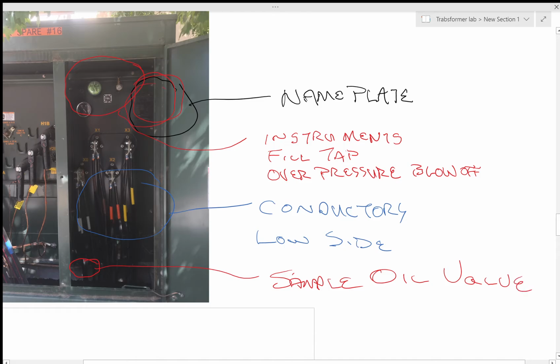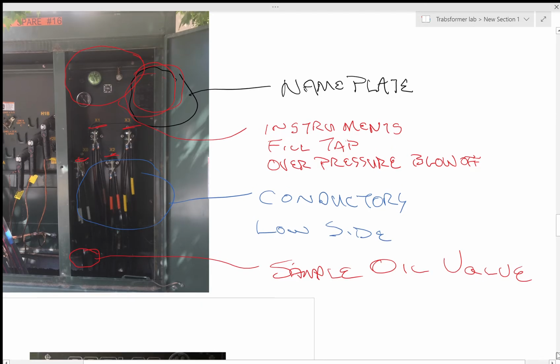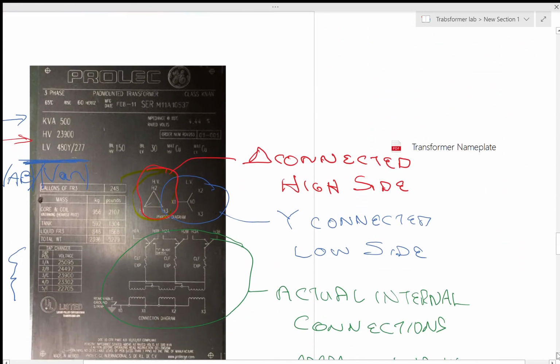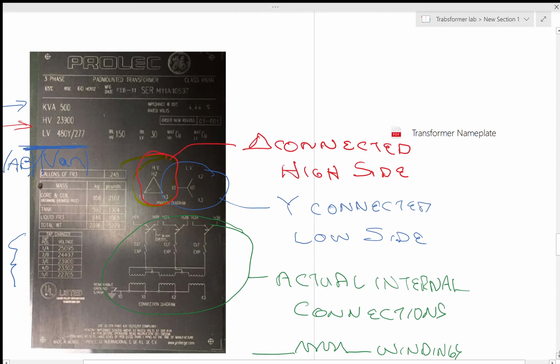And I can go in there and pull a sample of the oil, send it off to somebody, and they can tell me whatever is wrong with it. And then if you look in here, you'll see that you have an X0 value, an X1, an X2, and an X3. We'll get a little bit more into that. That's the low side. High sides are always H, low sides always X. So here's the nameplate, and it tells you everything there is to know about this transformer.